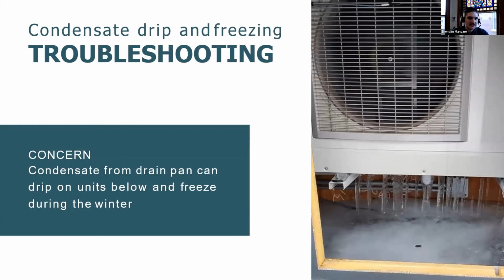The second one is condensate, drip, and freezing. These pieces of equipment produce a lot of water from the drain pan, especially when it gets below freezing. For the system as installed, we've been working on a couple of solutions to try to keep that from dripping on the units below and on the piping. But for future projects, we're either just mounting them all on quick sling ground mounted racks or staggering the heat pumps.